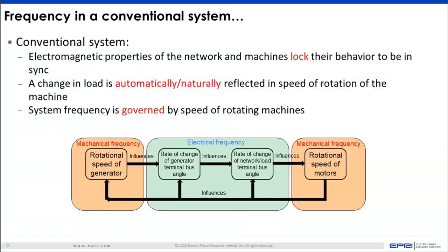What motivated us to go down this route is that in a conventional system, you have frequency, which is very much governed by the electromagnetic properties of the network. So what happens is that the machine and the network, because of laws of electromagnetism, lock their behavior and they're in sync with each other. So change in load is automatically or naturally reflected in the speed of rotation of the machine.